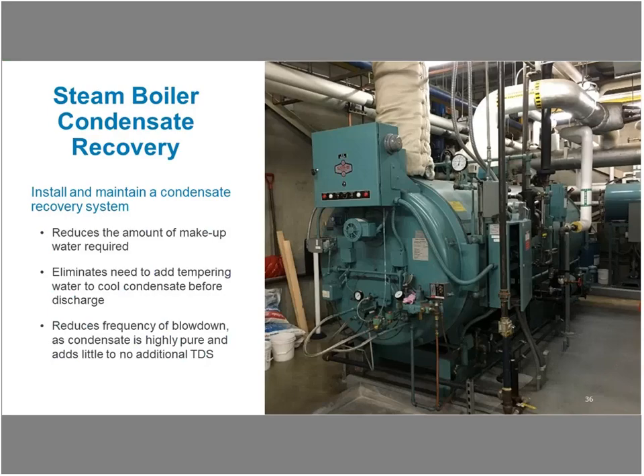The most important feature of an efficient steam boiler system is capturing steam condensate and returning it to the boiler. The water savings are threefold. Return of this high-quality hot water reduces water use and energy demand on the boiler system. It also eliminates the need for tempering water to cool the condensate before it is discharged. Lastly, it reduces the frequency of blowdown since the condensate is high-quality water with very low mineral concentration. Steam condensate recovery also results in energy saving. Since steam condensate is very hot, it just requires a lot less energy to reheat and produce steam all over again.